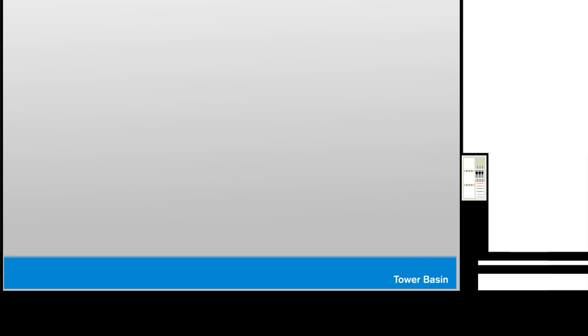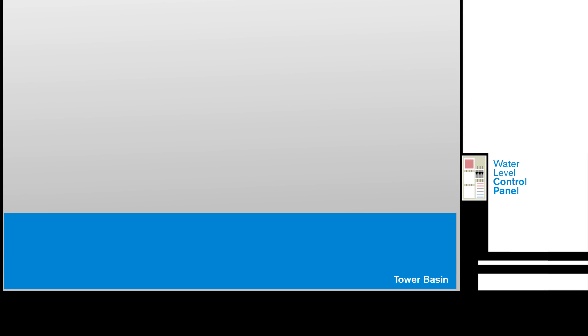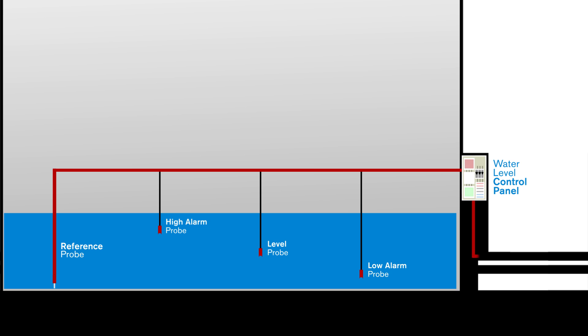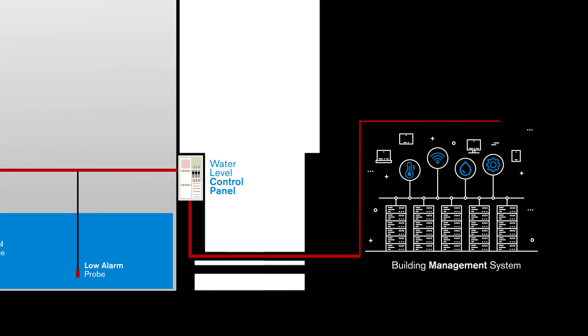This water level panel uses conductivity as a means to determine the level of the water in the basin of the cooling tower. It conducts electricity from a reference probe hanging in the water to other probes that represent different level heights in the cooling tower. This is used in lieu of using a float valve when you're looking for more information back from the control panel to the building management system.